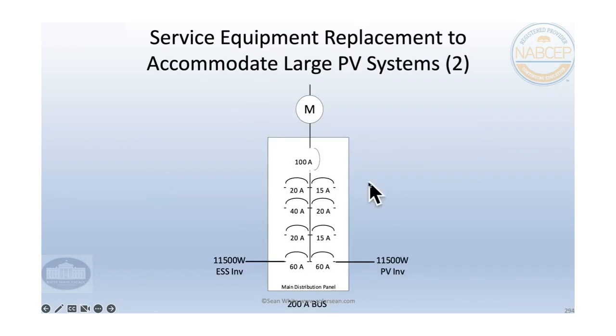Here's another neat one that's like one of the best ways of doing things. Say somebody has a 100 amp service, is to just change the panel board out. So you've got a 100 amp main breaker on a 100 amp panel board. You switch it out for a 200 or 225 amp bus bar, and you keep that 100 amp breaker, and you are very future proof. You can plug in all your electric vehicles for the next 25 years. And all these energy storage systems and PV systems, we'll show some neat pictures of that.